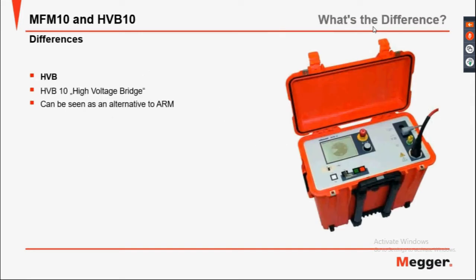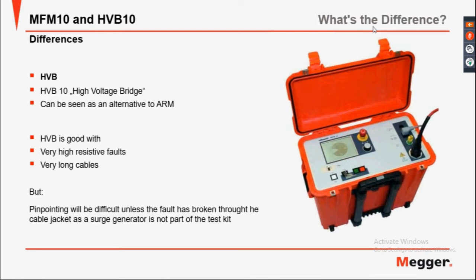The HVB10 is a high voltage bridge, which is an alternative to the Murray (resistance) method. The HVB is good with very high-resistant faults and very long cables, up to approximately 200 km. However, pinpointing will be difficult unless the fault is broken through the cable jacket, and the surge generator is not part of the test kit.